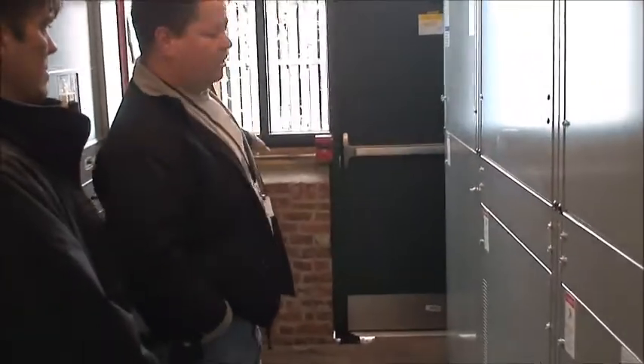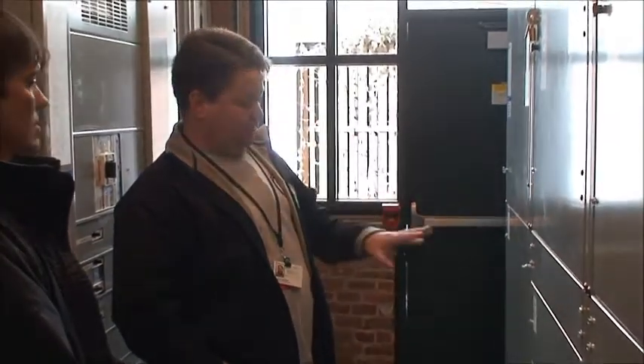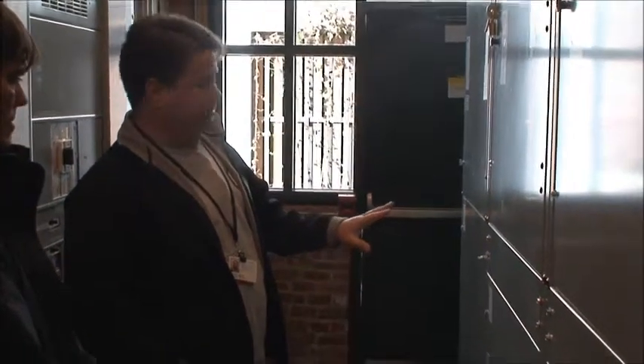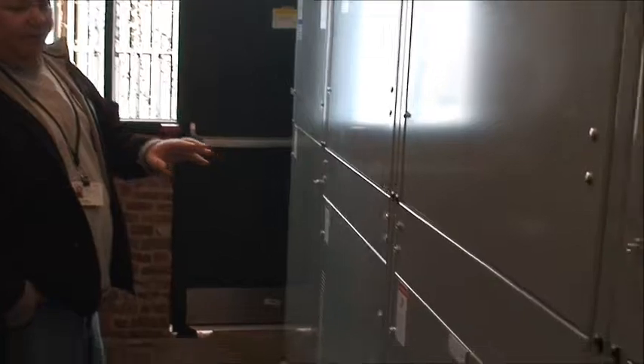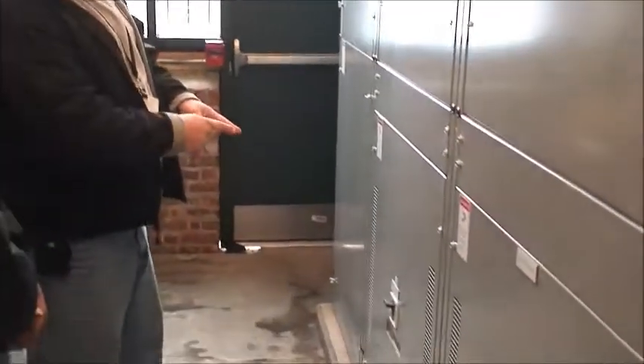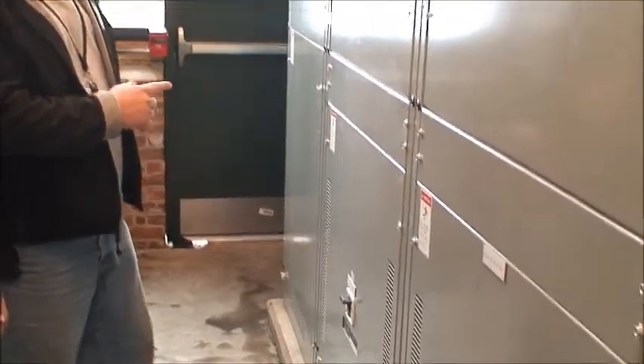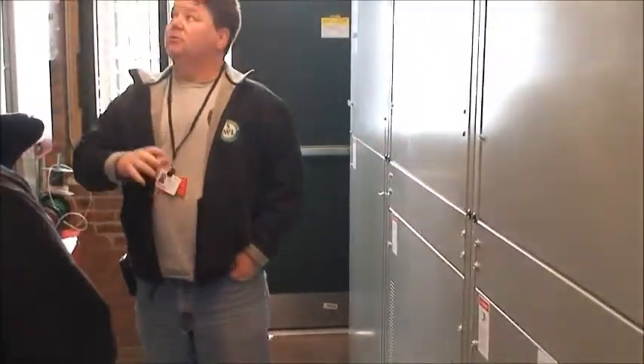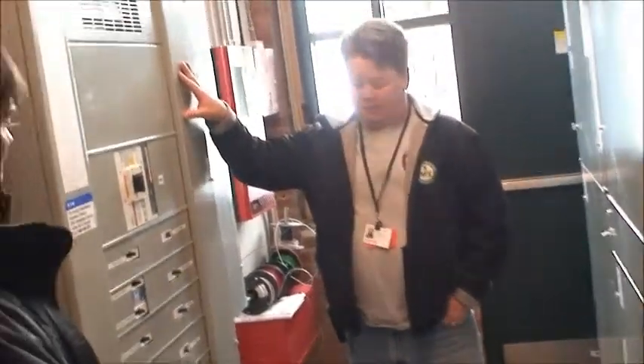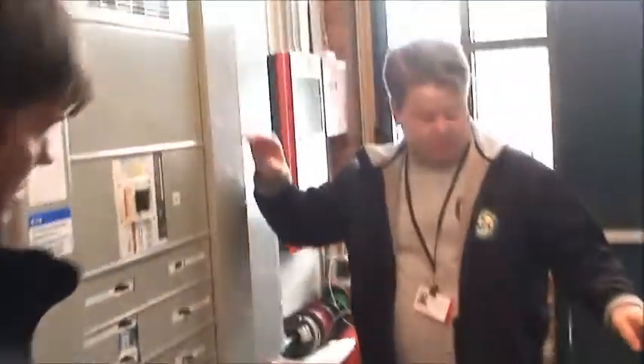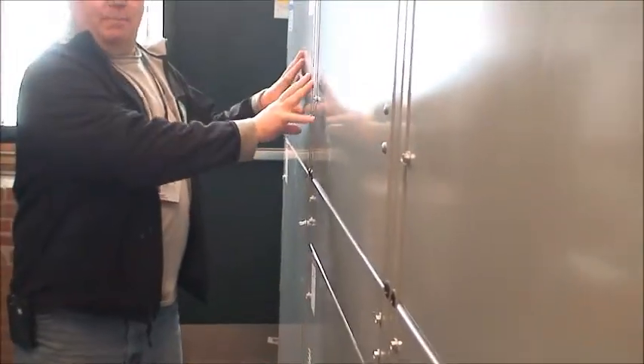All your conduits come in underground from your N-Star outside. Your 2,000 amp bus in the back of this is tapped 3 times. You have your house breaker, which does all the public, which is connected to this panel here, underground. So the feeder comes in, obviously underground, to the main bus.